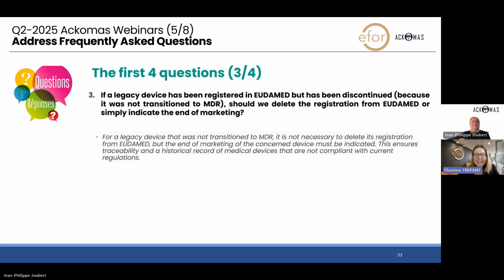If a legacy device has been registered in EUDAMED but has been discontinued because it was not transitioned to MDR, should we delete the registration from EUDAMED or simply indicate the end of marketing? So, of course, you can delete the data in EUDAMED. It's a manual transaction to do that. But I do not recommend that for 2 reasons. First, we don't know the consequence of doing that. And the second is we are losing traceability of what is done.